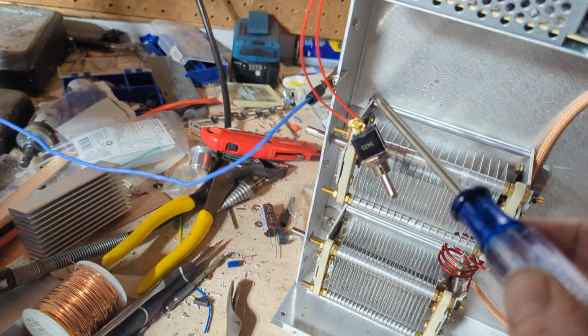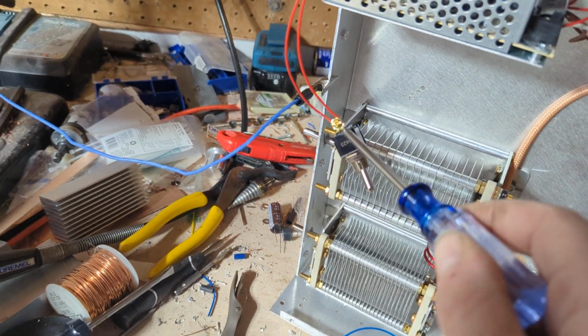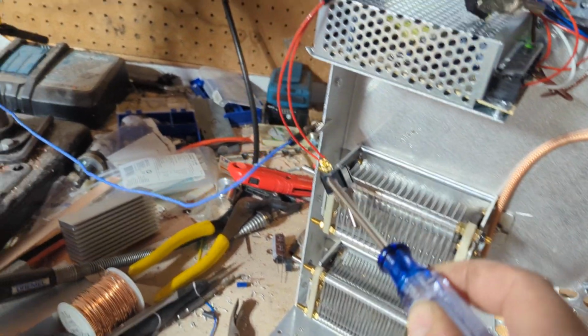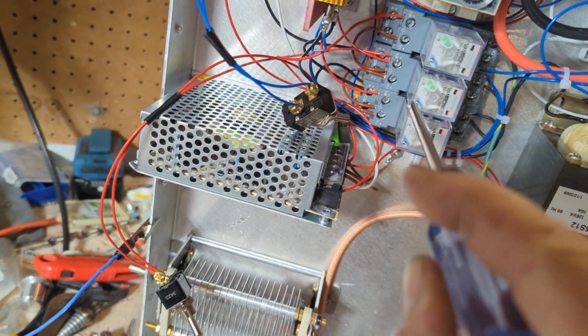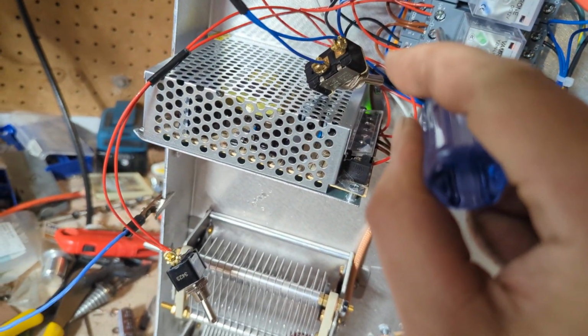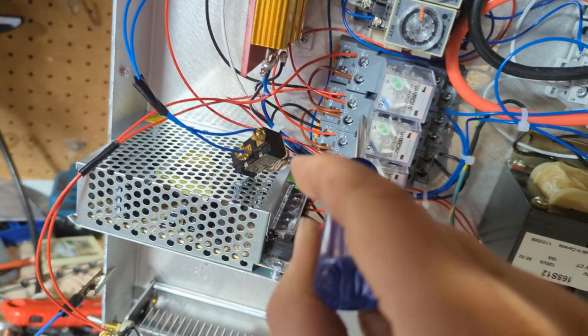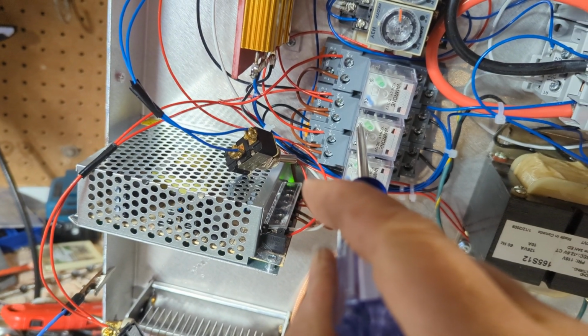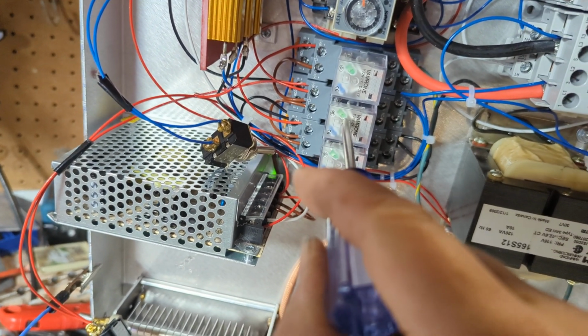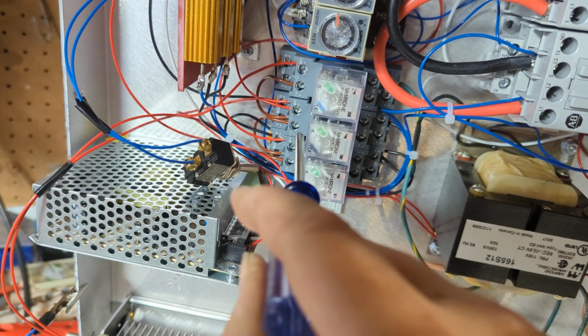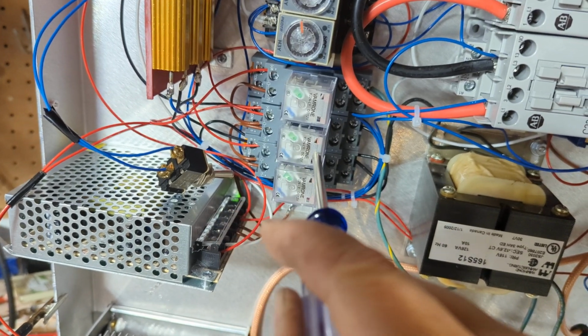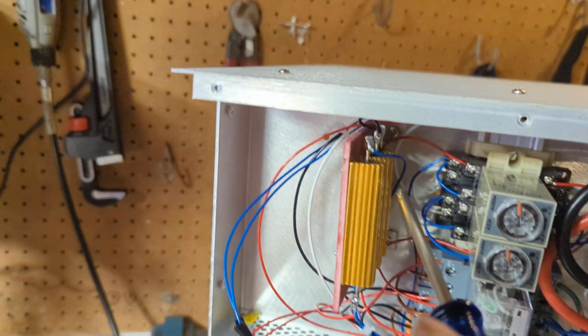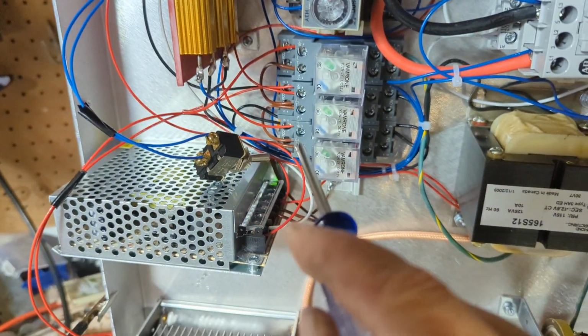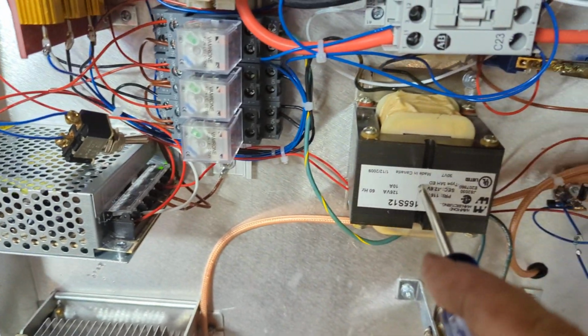Then we have this switch right here. It takes the 12 volts from the positive, goes through the switch, and goes to this first relay right here. It immediately fires up this relay, and it allows 110 volts on the other side of the set of contacts to go through there, through this bank of resistors, and into the filament transformer.